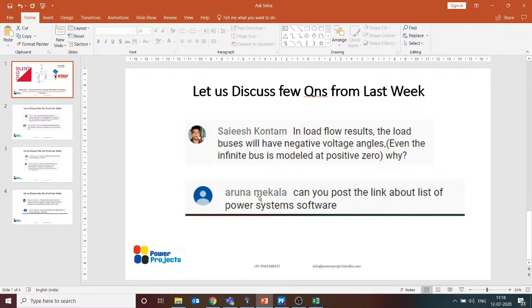Let me re-stress that answer. If you have sufficient reactive power capability from the generators to meet the reactive power demand of your system in an islanded mode, you need not really do any reactive power compensation, because the generator itself will compensate it. You can just keep the generator in voltage control mode with respect to the voltage. That's more than sufficient. It automatically takes care of whatever reactive power is in the system. But if the reactive power demand in your system is more than the reactive power capability of the generators, then there is no other way. You need to put up capacitor banks to compensate.